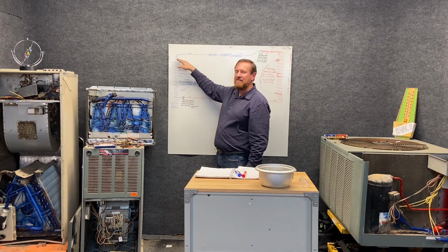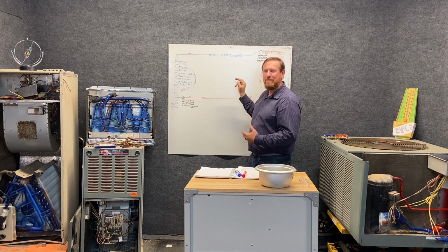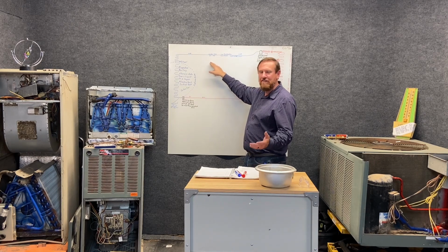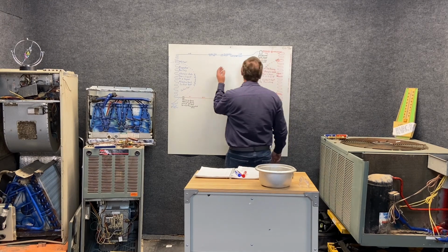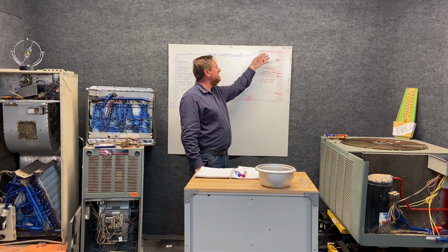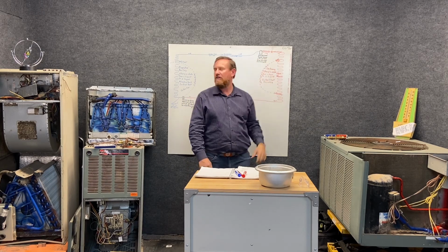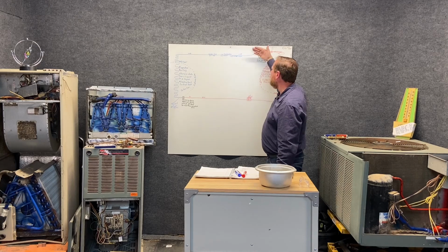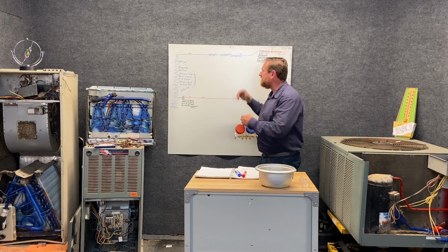but by the time it left, it was 100% vapor. That's very important because this is a vapor pump. So it sucks through the suction line, which is also a gas line, so we'll call it a vapor line. It's also correct, a vapor line, low pressure, low temperature, superheated vapor, and then discharge line, high temperature, high pressure, superheated vapor, condensing in the majority of this coil. We then have a liquid line. Notice the liquid is far away from that compressor. That's very important. Our whole cycle happens again.